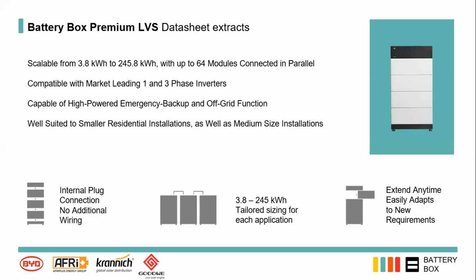Some properties about the LVS. You can scale it from 3.8 kilowatts all the way up to 245 kilowatts, giving a large flexibility of the amount of power available. It's compatible with all the market-leading single-phase and three-phase inverters, and it's very capable of high-powered emergency backup and off-grid functionality. This battery is typically used in the smaller residential installations, as well as any medium-sized installations. Because of the tower design, you can extend quite easily at any point in time.